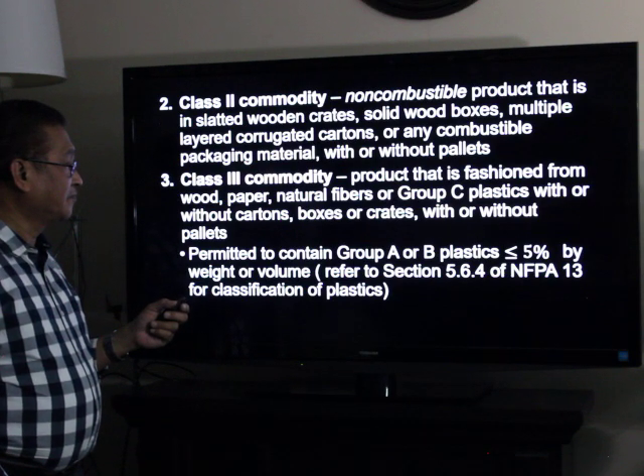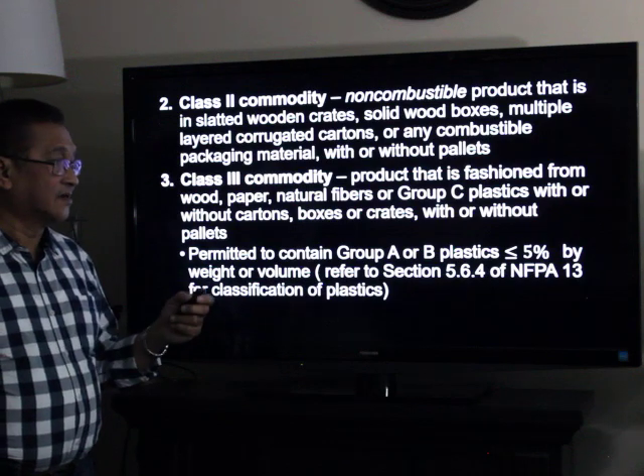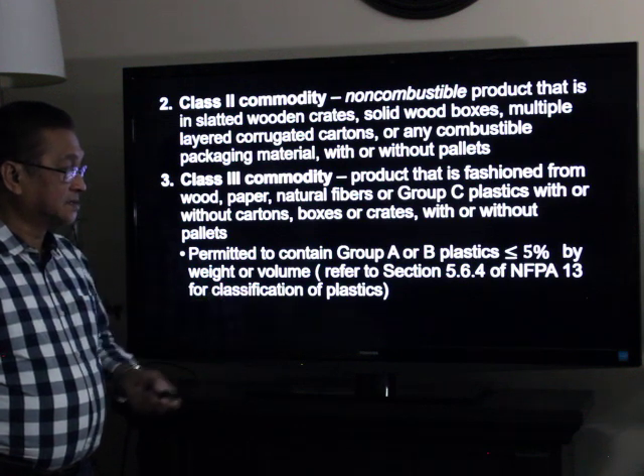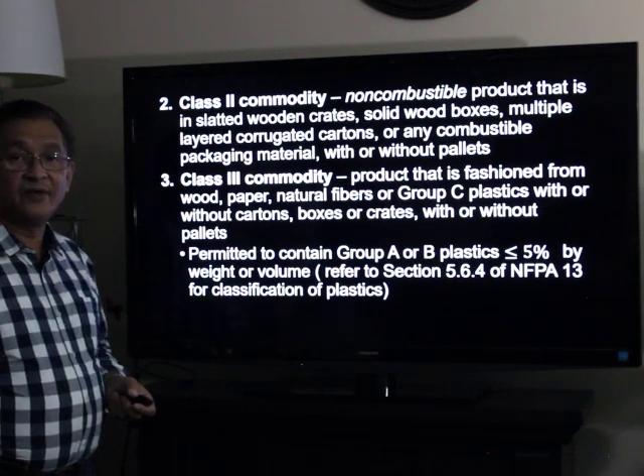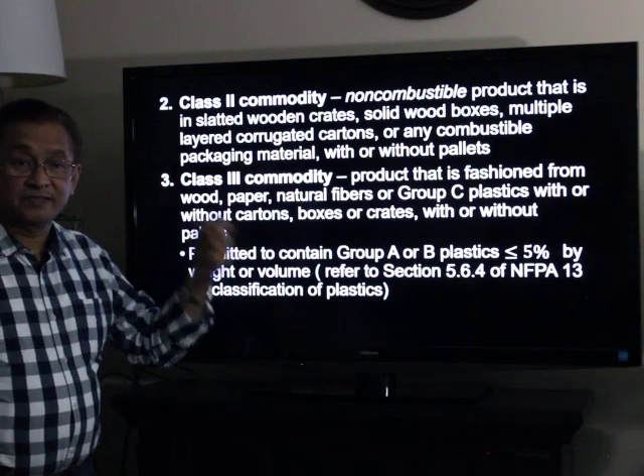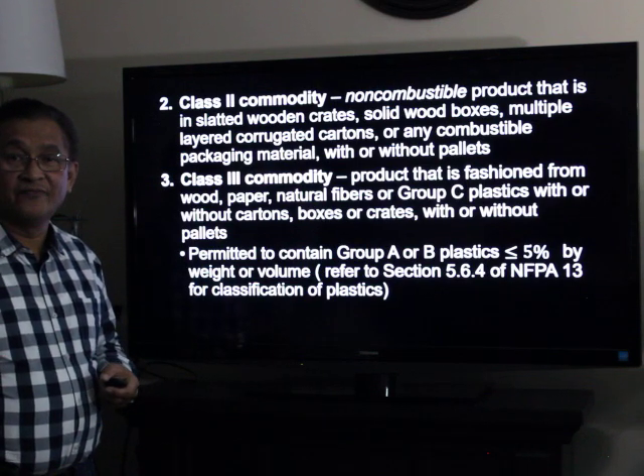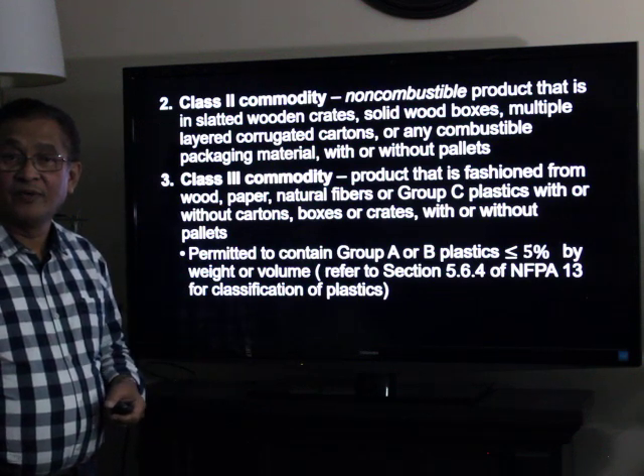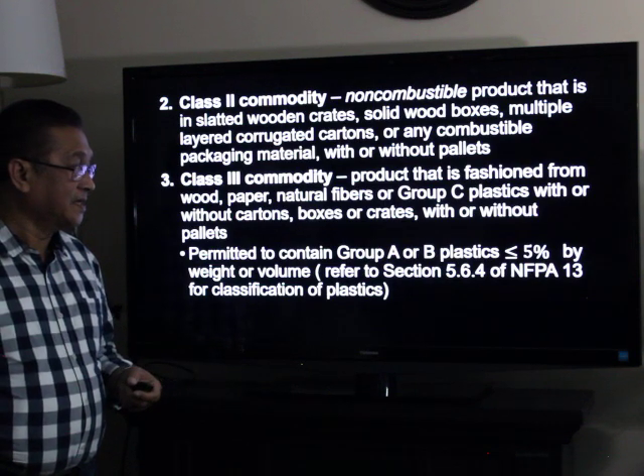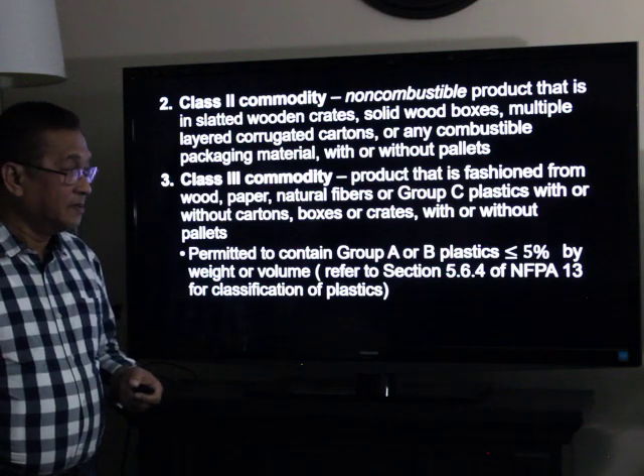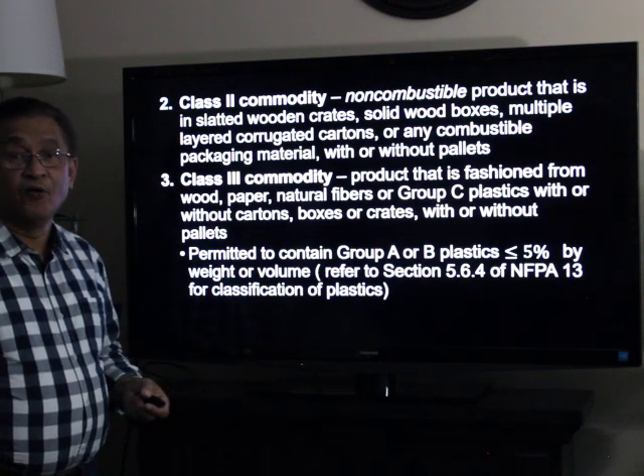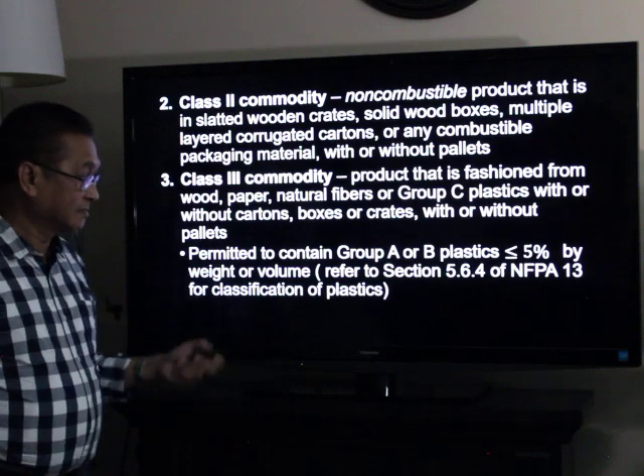Class three commodities are permitted to contain Group A or Group B plastics less than five percent by weight or by volume, as detailed in Section 5.6.4 of NFPA 13 for classification of plastics. Examples of Group A plastics include polyethylene, acrylic, and flexible PVC. For Group B, an example is silicone rubber. For Group C, examples include polyvinyl fluoride and phenolic.